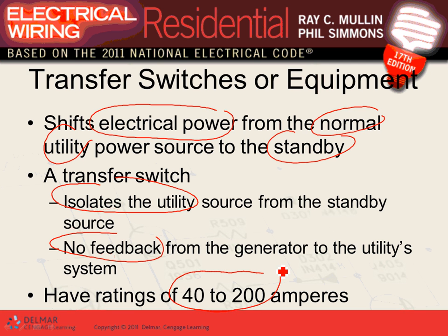Sizes, you can get them from 40 all the way to 4,000 amps. Not 200. For dwellings, typically 200. But for non-dwelling, you can go as high as 4,000 amps on these. Typically, what we use, guys, 40 amps are common, 60 amps, 100 amps are common. 40 amps are very common in dwellings, because all you need is to back up 40 amps of your loads, the critical ones.